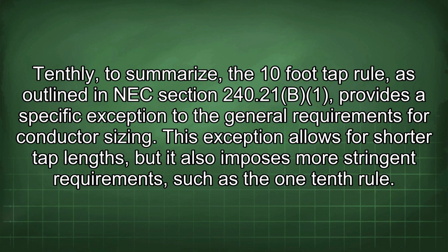Tenthly, to summarize, the 10-foot tap rule, as outlined in NEC Section 240.21(B)(1), provides a specific exception to the general requirements for conductor sizing. This exception allows for shorter tap lengths, but it also imposes more stringent requirements, such as the 1/10 rule.